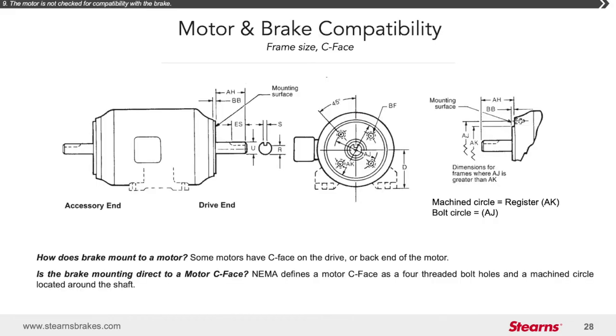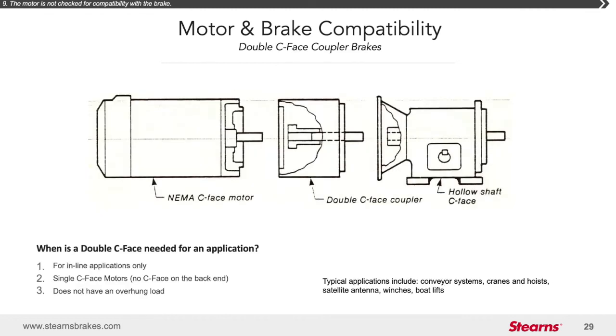The majority of motor brakes are face-mounted brakes that typically mount to the accessory end of a motor. So you want to check with the motor manufacturer to assure that a motor can accept a brake. If there's not an accessory end mount, there are other options, which we'll talk about in the next few slides. If a motor is not equipped with a mounting face on the non-drive end, you can consider a double C-face coupler brake that will mount to the drive end of the motor.